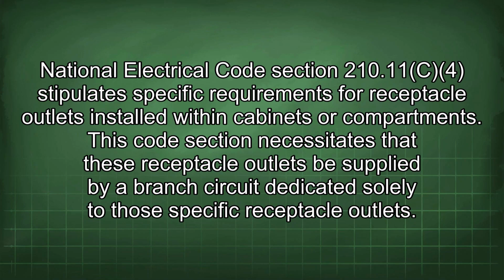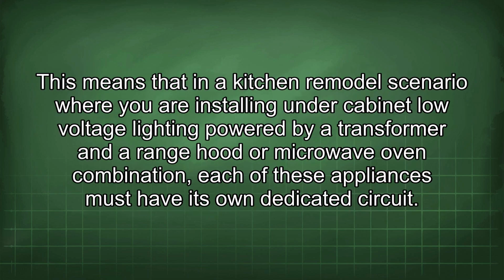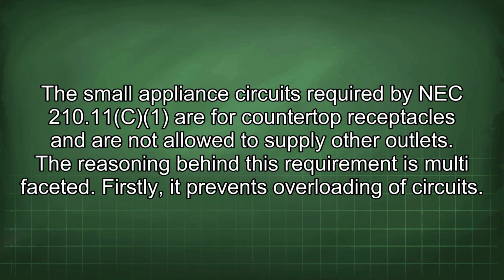National Electrical Code Section 210.11(C)(4) stipulates specific requirements for receptacle outlets installed within cabinets or compartments. This code section necessitates that these receptacle outlets be supplied by a branch circuit dedicated solely to those specific receptacle outlets. This means that in a kitchen remodel scenario where you are installing under cabinet low voltage lighting powered by a transformer and a range hood or a microwave oven combination, each of these appliances must have its own dedicated circuit. Small appliance circuits required by NEC 210.11 are for countertop receptacles and are not allowed to supply other outlets.